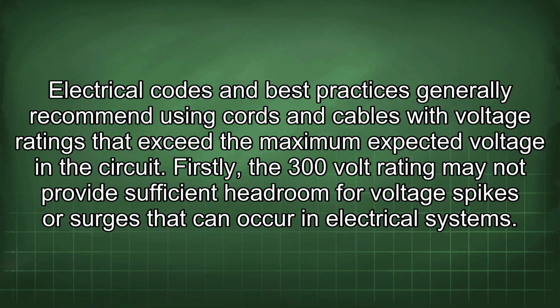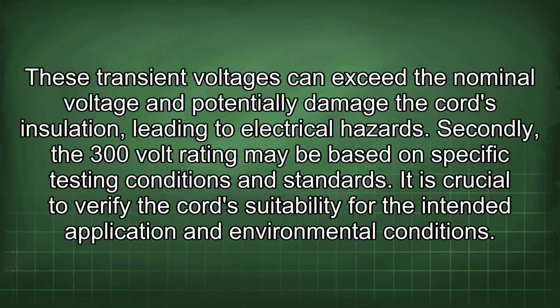Firstly, the 300-volt rating may not provide sufficient headroom for voltage spikes or surges that can occur in electrical systems. These transient voltages can exceed the nominal voltage and potentially damage the cord's insulation, leading to electrical hazards. Secondly, the 300-volt rating may be based on specific testing conditions and standards. It is crucial to verify the cord's suitability for the intended application and environmental conditions.